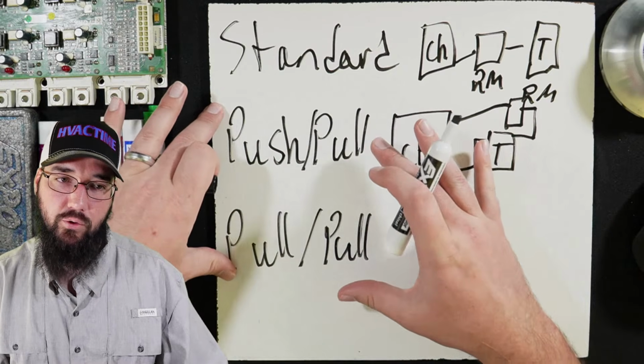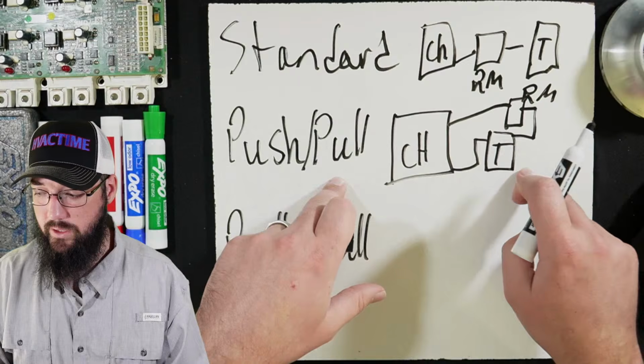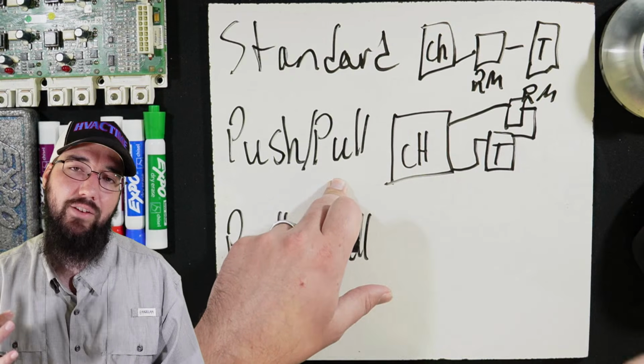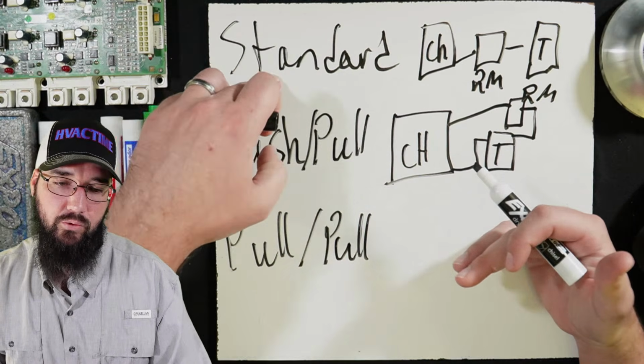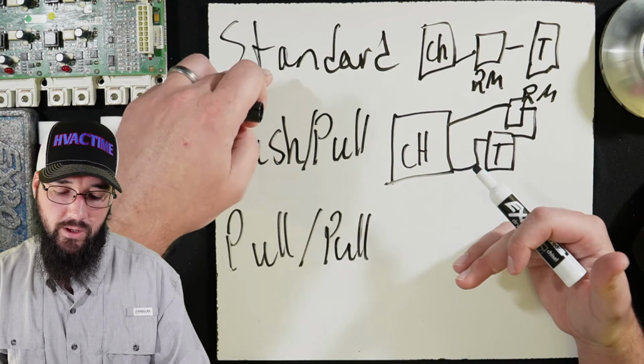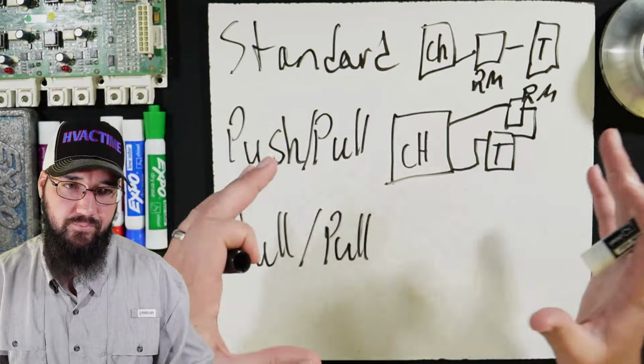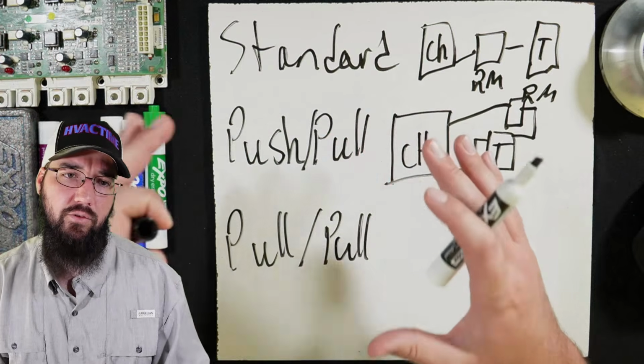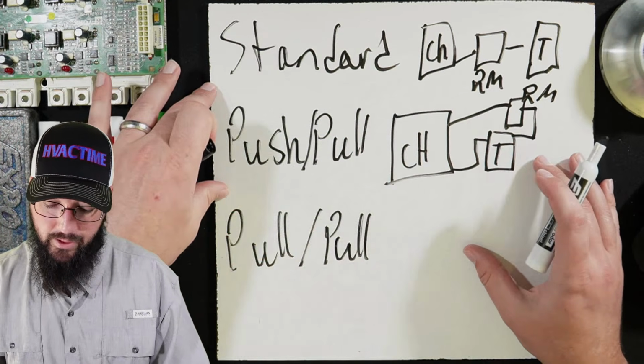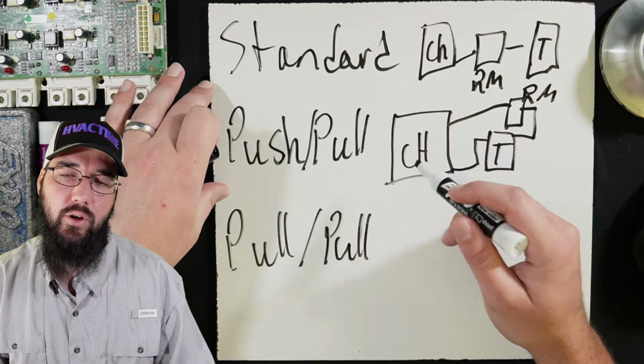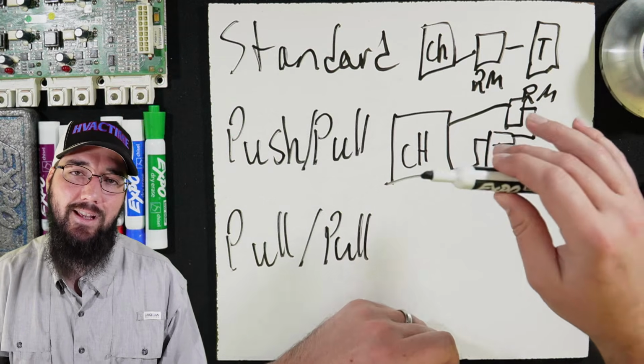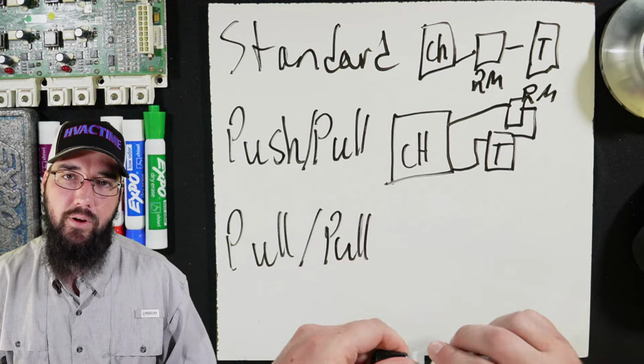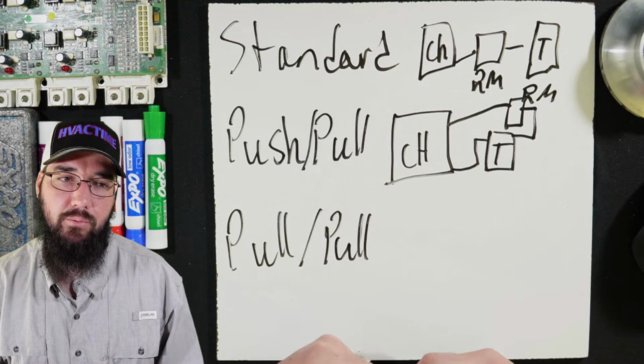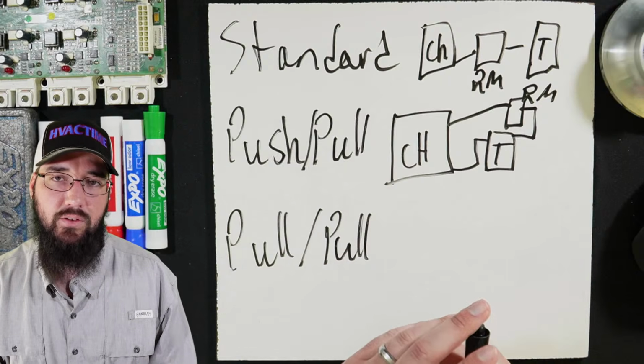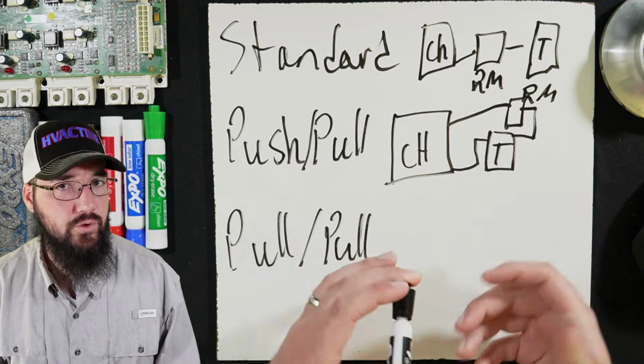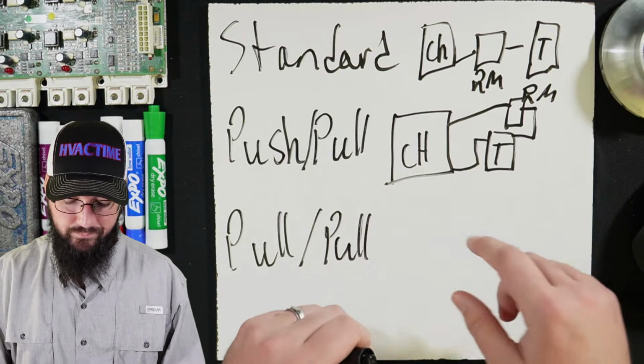Both of these are kind of a two-phase process. Phase one is we're getting all the liquid out like this. Phase two would be going back over to a standard recovery, which would then remove all of the vapor. And the whole point of why this matters is when we're trying to do a recovery and we can't get all the liquid out, boiling that liquid refrigerant out of the system, especially at the scale of some of these systems, takes a huge amount of time. Like it's a huge amount of time.